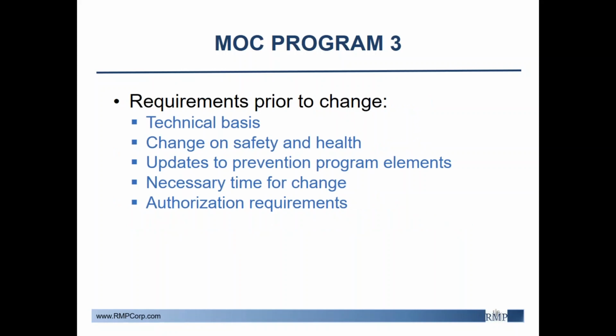MOC procedures shall assure that the following considerations are addressed prior to any change: the technical basis for the change, the impact of the change on safety and health, the necessary time period to implement the change, and authorization requirements for a proposed change. This usually includes the originator, the ops supervisor, and plant supervisor.